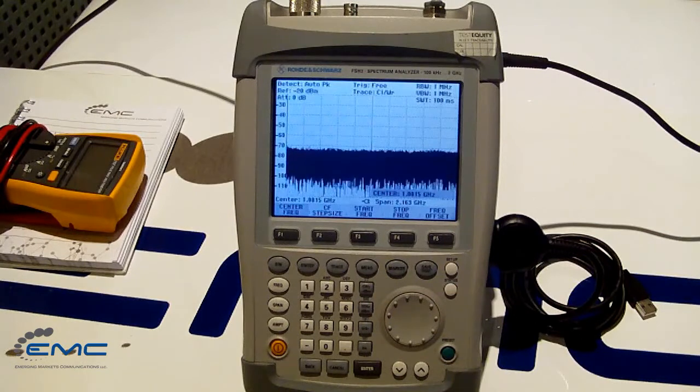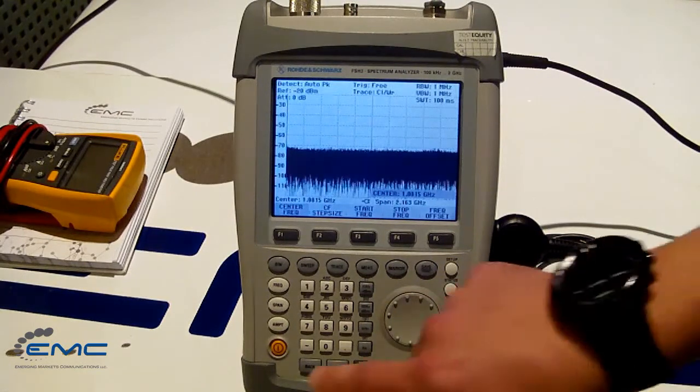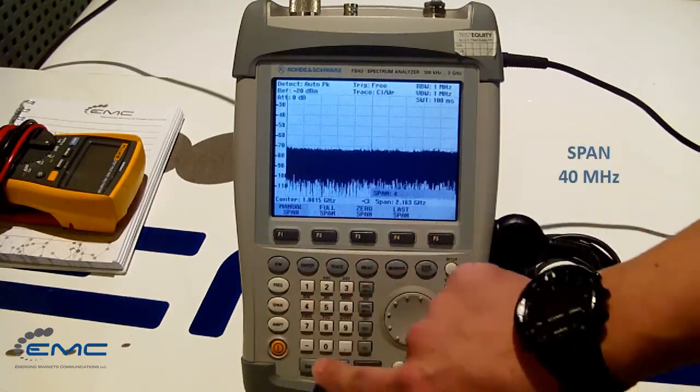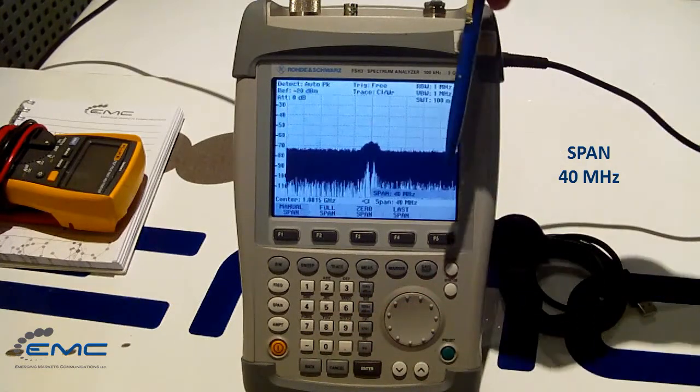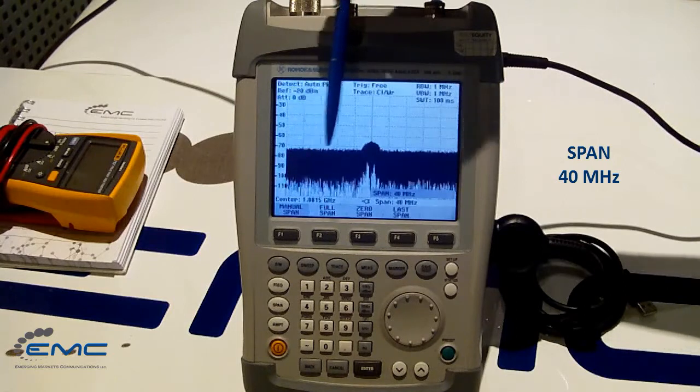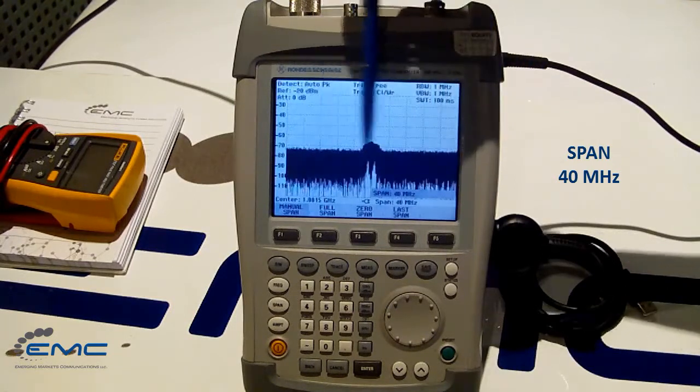Now, let's change span, for example, to 40 MHz. Now our display shows us only 40 MHz range of the trace we have here.